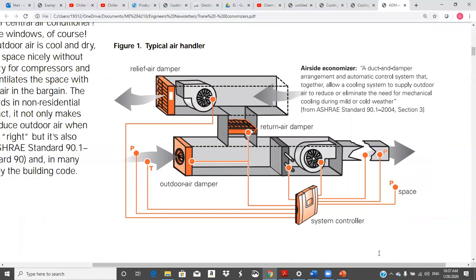So that's what we want to do. We want to compare the enthalpy here, because I can get that across my coil, to the enthalpy outside. And I want to select the one that's less. Less energy into the coil, less load on the coil. Everything's good. Okay?